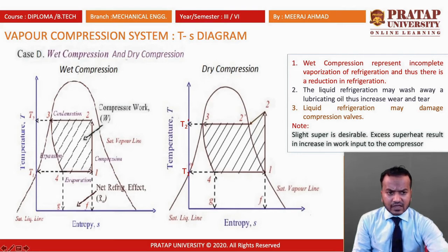Thus there is a reduction of the refrigeration effect. Also, the liquid refrigerant may wash away the lubricating oil, which increases wear and tear of the compressor.